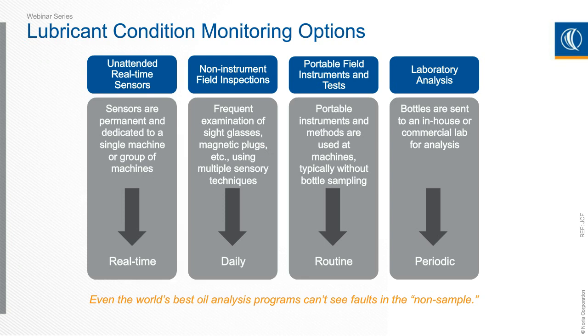So it's a technology-intensive method. We have to have sensors that can continuously collect data, such as on viscosity or contaminant levels like moisture and particles, or chemistry of the oil, and can alarm when these conditions become abnormal. There's in the range of 50 to maybe 75 sensors on the market today that can provide this capability. Many of them are quite expensive.